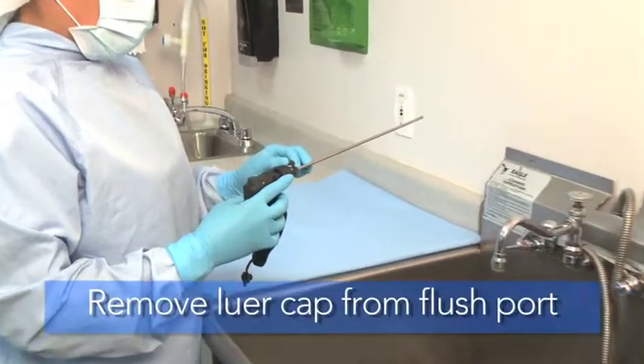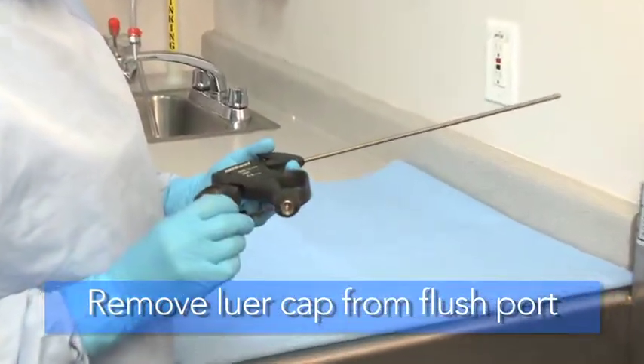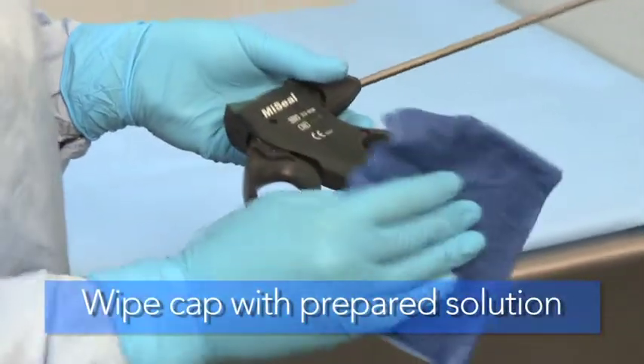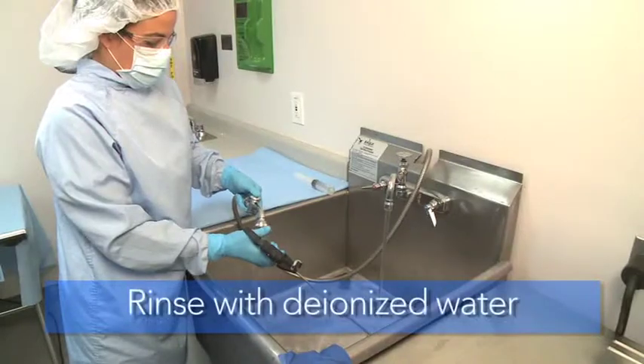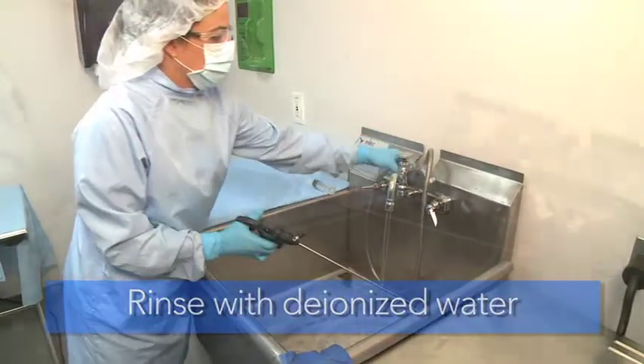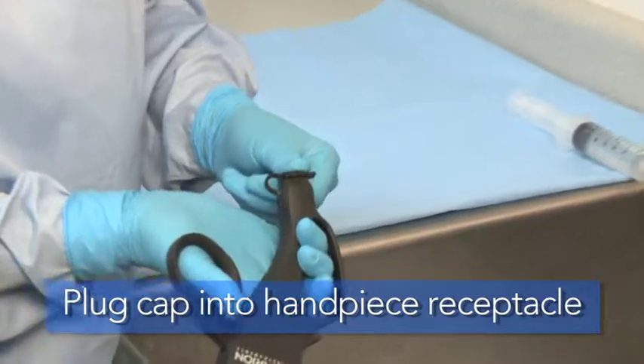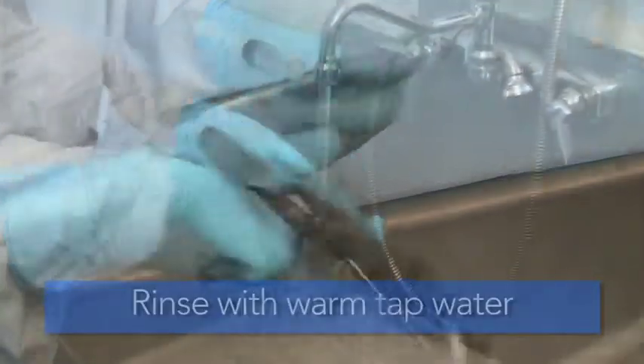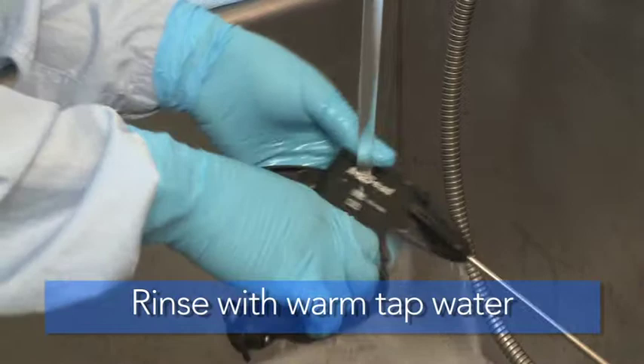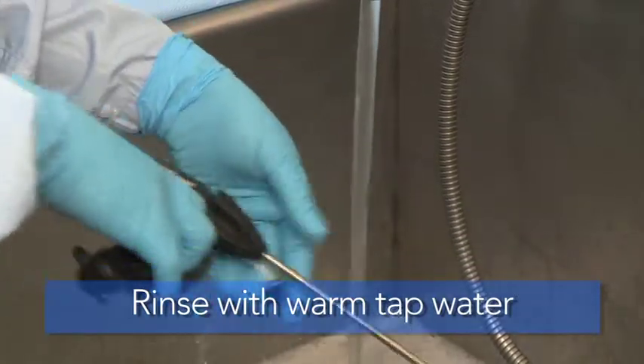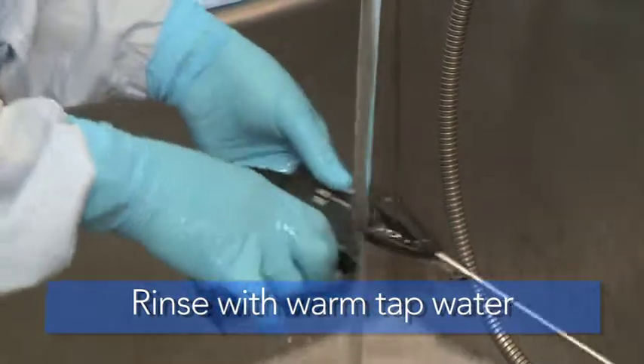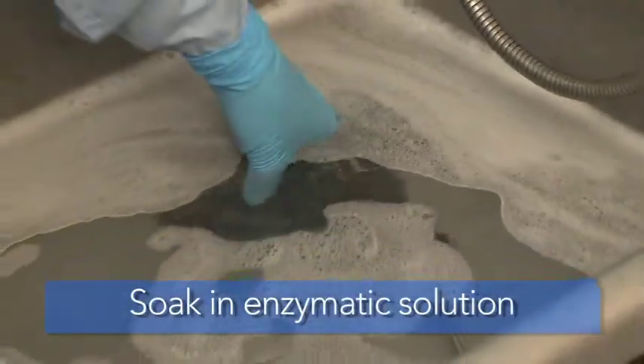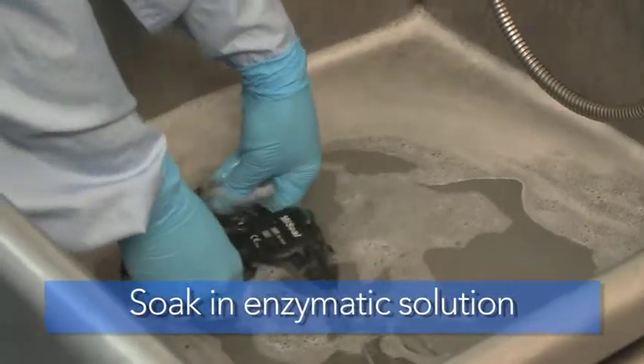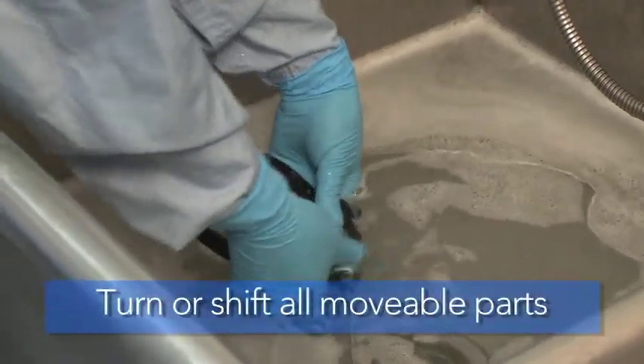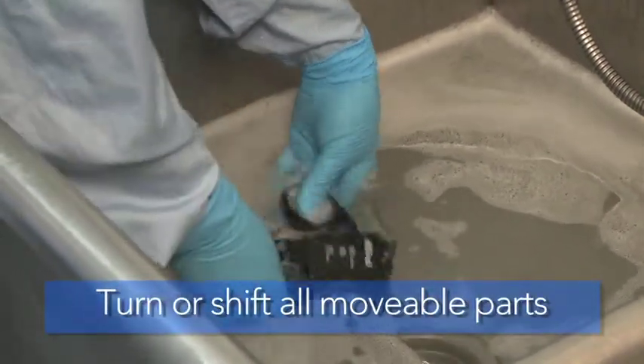Remove the luer cap from the flush port on the rotator knob. Unplug the receptacle cap from the bottom of the handpiece. Wipe down the cap with the prepared enzymatic solution and rinse with deionized water. Plug the cap into the receptacle at the bottom of the handpiece. Rinse the device with warm tap water for a minimum of 1 minute. Soak the device in the prepared enzymatic solution for 10 minutes. Make sure all movable parts, including the triggers and rotator knob, are turned or shifted.